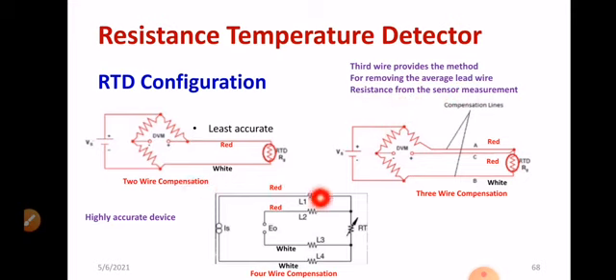If I talk about 4-wire compensation, you can see 2 red wires and 2 white wires. So this is highly accurate. If you are still looking for high accuracy, do prefer 4-wire compensation. It is somewhat expensive, however it gives an accurate value of temperature. That means you will be measuring resistance, and that value can be compared with the suitable temperature. So this is known as the different R.T.D configurations. From this graph we can say that the 2-wire compensation method is least accurate compared to 4-wire compensation.